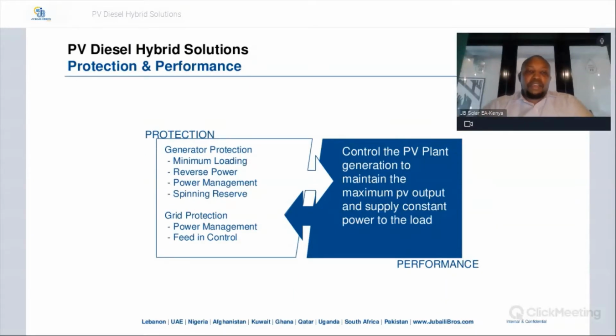When you come to the protection side, we have generator protection. You want protection when it comes to minimum loading. You need protection when it comes to reverse power. Power management, you need to have good power quality. You also need to look at spinning reserve. You don't want your generator to constantly switch on and off, on and off. As well as from the grid, you want to make sure that you have good power quality from the grid, as well as control feed-in, because you have areas where you are not allowed to send power back to the grid. So you need to set feed-in or limitation control.